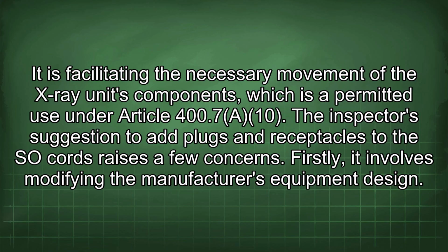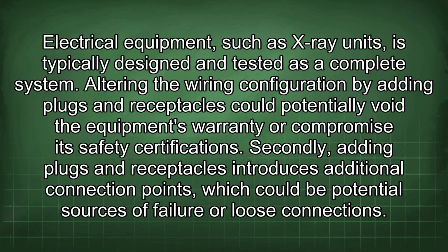Firstly, it involves modifying the manufacturer's equipment design. Electrical equipment, such as X-ray units, is typically designed and tested as a complete system. Altering the wiring configuration by adding plugs and receptacles could potentially void the equipment's warranty or compromise its safety certifications.